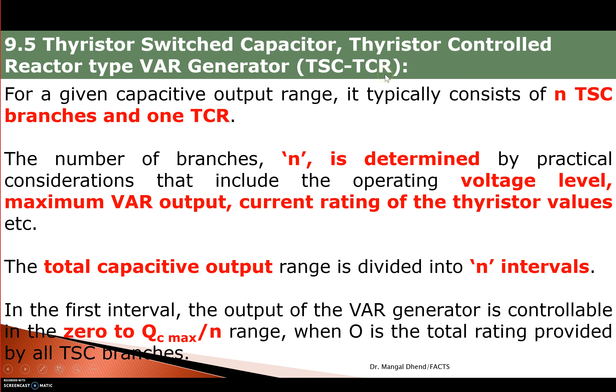The TCR will go on absorbing power even generated by TSC, and you can get smooth variable control if TCR combination is used. N, the number of TSC branches, is determined by the voltage level and maximum VAR output required. If maximum VAR output is 40 and one TSC is 10, then N equals 4. If one TSC gives 20, then N equals 2 for 40 KVAR. The current rating of the thyristor valves is important, and N can be decided accordingly.